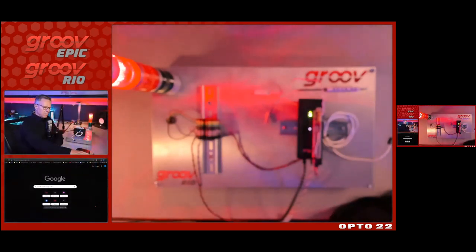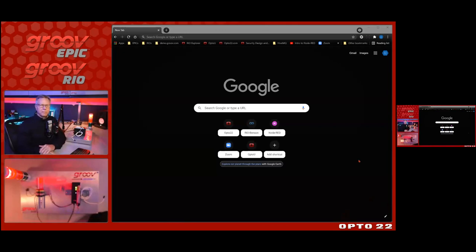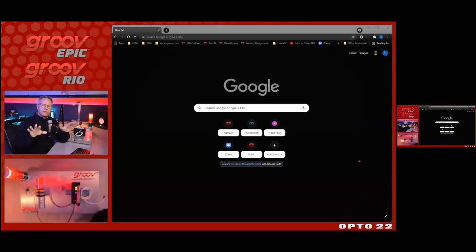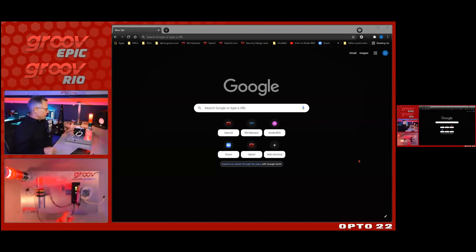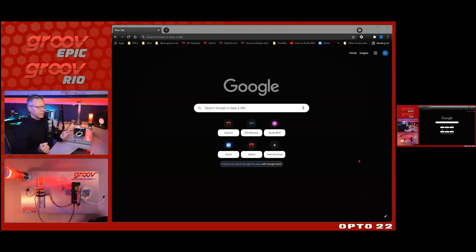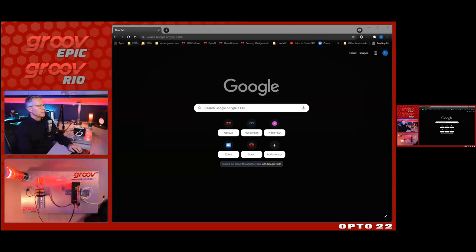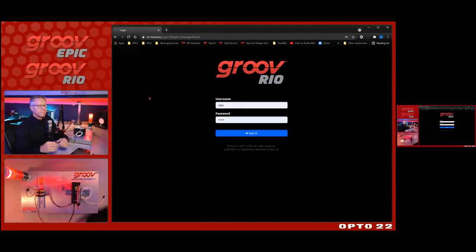I'm going to log into the Groov RIO to show you how the configuration occurs. Both Groov EPIC and Groov RIO are designed for the plant floor — rated minus 20 to 70 degrees C, UL listed, Class 1 Div 2, DIN rail mountable. The RIO runs on Power over Ethernet, making it simple to install for quick sensor data collection. These devices are secure, allowing access only over a secure channel — the web pages are served directly from the device with HTTPS and a valid certificate.